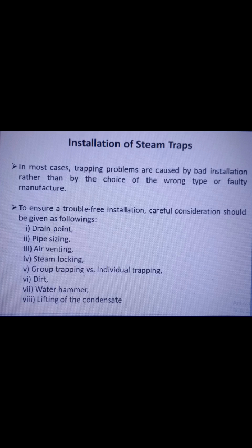Fourth one is steam locking. Steam locking is similar to air binding, except that the trap is locked shut by steam instead of air. A typical example is a drying cylinder.